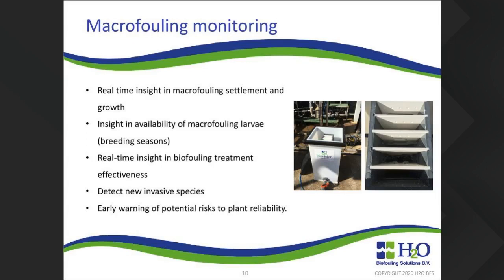So if there is a new invasive species arriving in the area of your utility, if it starts to enter the cooling water system, this monitor will give you an early warning, which gives you the opportunity to adjust your chemical treatment and dosing to make sure that it doesn't foul your system if the species prove to be more resistant than the existing ones for your chemical dosing. It's an early warning for potential risks to plant reliability, more or less.